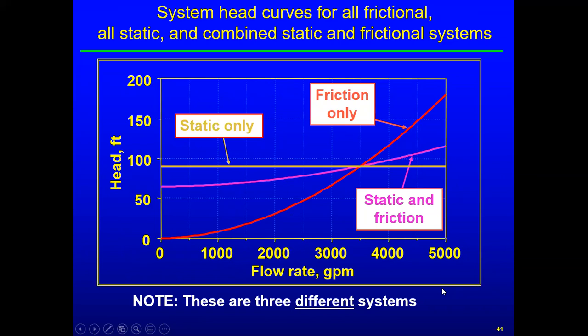There are three types of system curves. A zero static head (all-frictional) system curve passes through the origin. An intermediate system has significant static head — around 70 feet — with additional friction on top. A static-dominated curve is nearly flat — while there's no truly static-only system (any fluid flow creates some friction), some systems are so dominated by static head that the curve appears nearly horizontal. Combining these with pump curves shows how each system type reacts differently to pump operation.